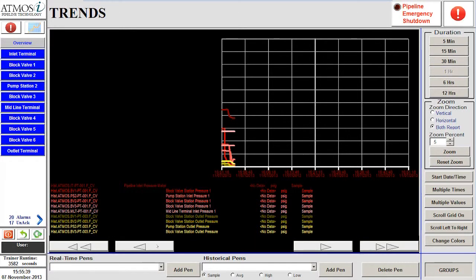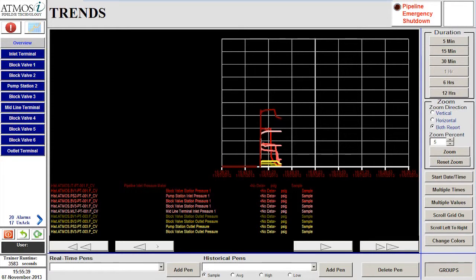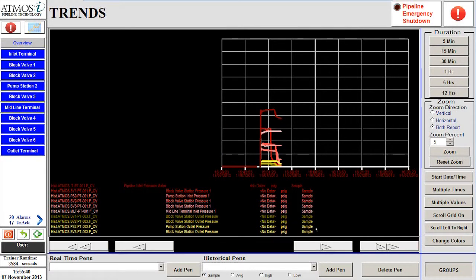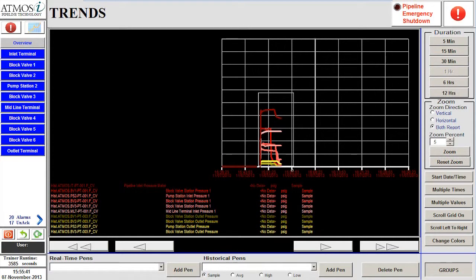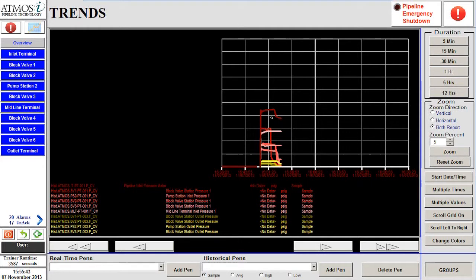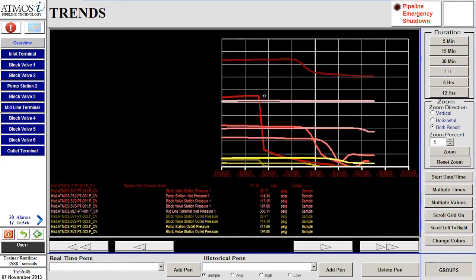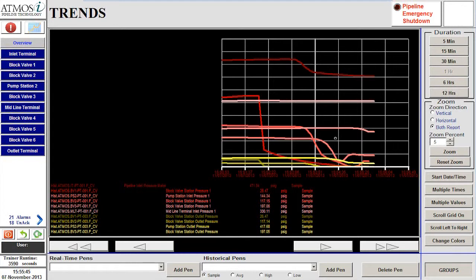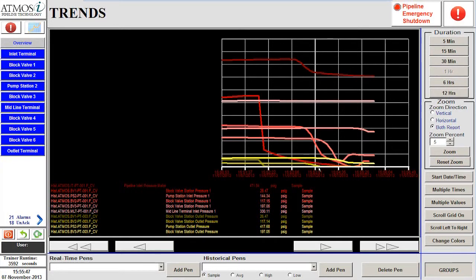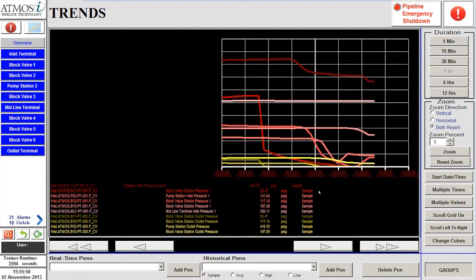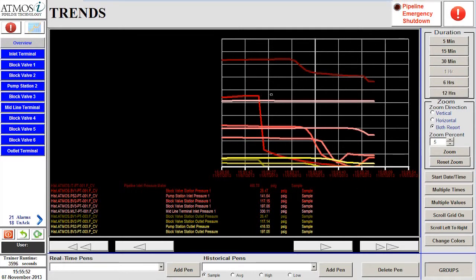Returning to the pressure trend and analyzing the data will show that the pressure between block valve 1 and block valve 2 is still decreasing. However, the pressures in the other sections appear to be stabilizing.